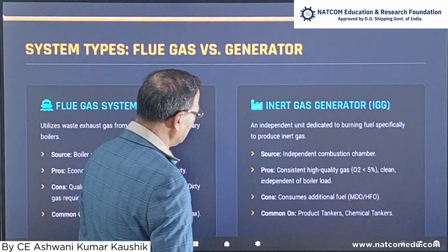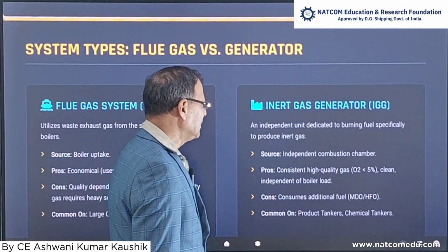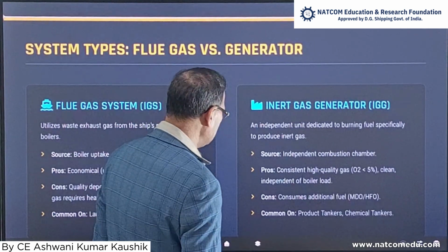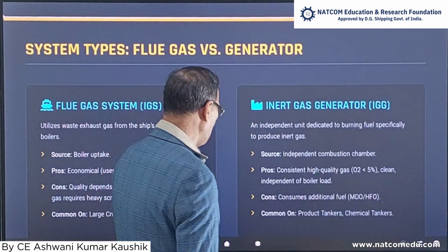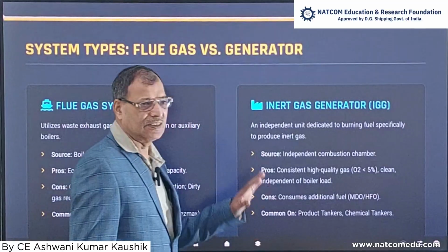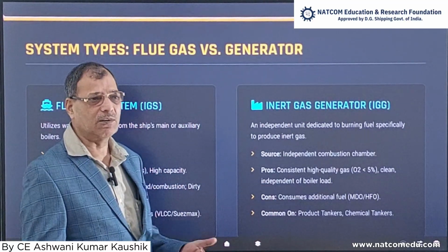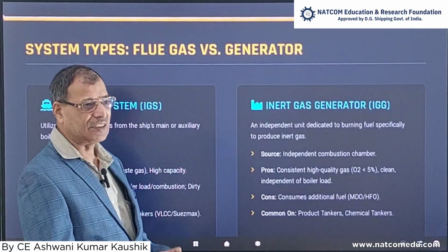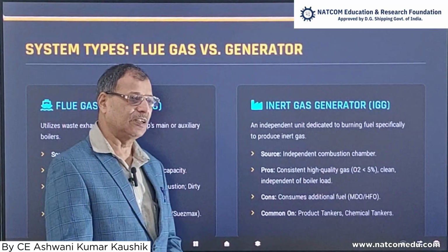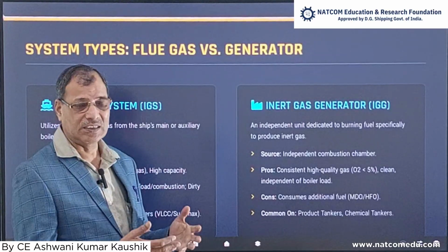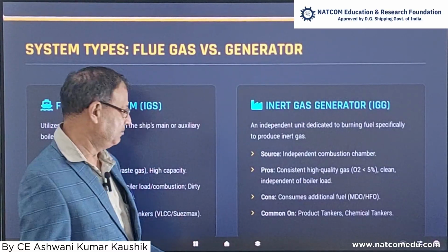Pro: constant high quality gas, with O2 less than 5%, clean, independent of boiler load. Consumption: additional fuel, MDO or HFO. Normally the IGG system is running on LSMGO. Nowadays there are plenty of restrictions on fuels, that's why they are using low sulfur marine gas oil.